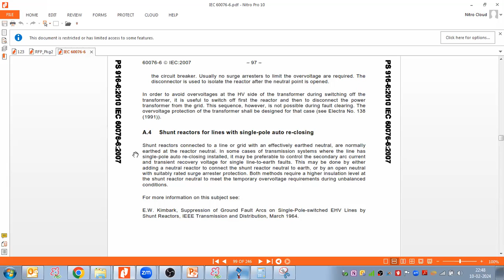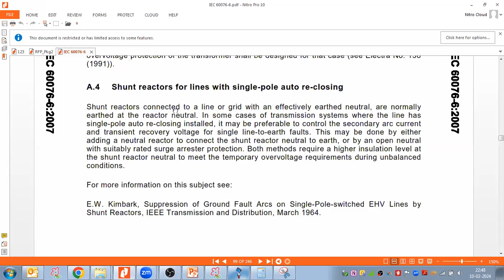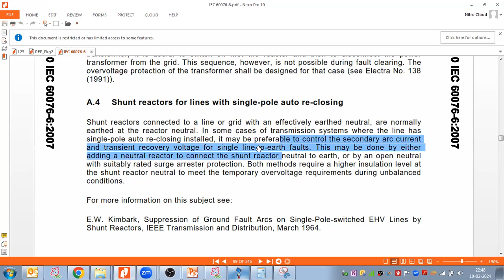So when I come here, this is the important part when I have read the standard. You see here, shunt reactor for lines, which in our case is with single pole auto reclosing. So this standard directly tells you that the NGR is required. Shunt reactors connected to a line with an effectively earthed neutral are normally earthed at the reactor neutral. In some cases, the transmission system where the line has single pole auto reclosing. What is single pole? What is three pole? What is auto reclosing? This topic I will take in the breaker module. As of now, please note down the concept. Put a star, and this reclosing we will cover in the breaker module. Or it would be better if you can check through Google and note it down as of now.